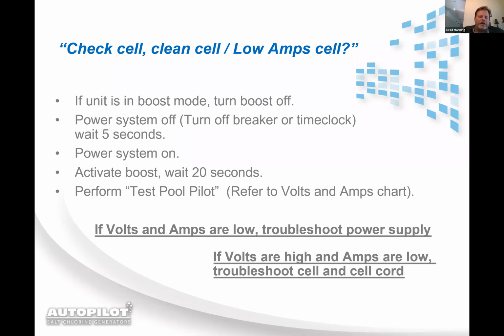And via that reading, you can use your volts and amps charts to determine where you need to start your troubleshooting. Typically, once you've done the test properly, if you're getting high volts and low amps, you're going to want to start troubleshooting at the cell and cell cord and work your way backwards towards the power supply. If you do this test properly and you get low volts and low amps, you want to start troubleshooting the power supply. You've more than likely got a bad power module or a blown fuse on the power module.